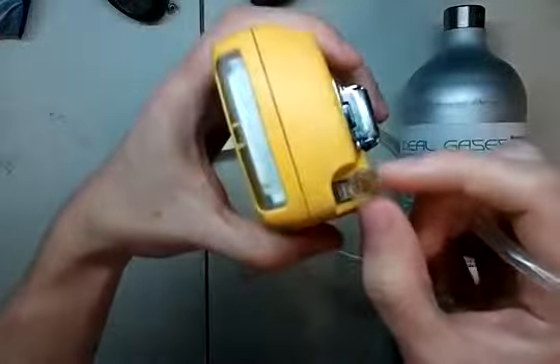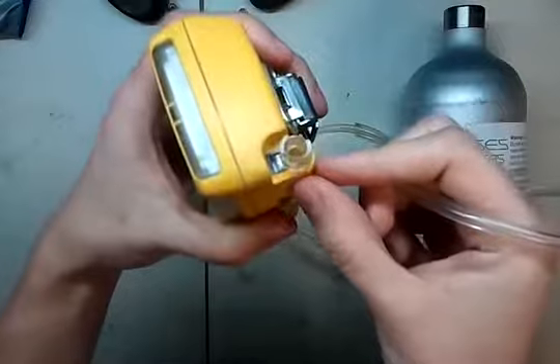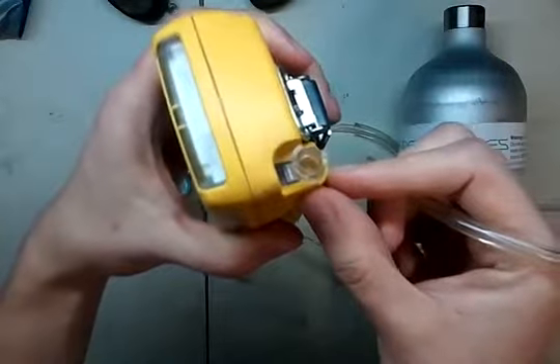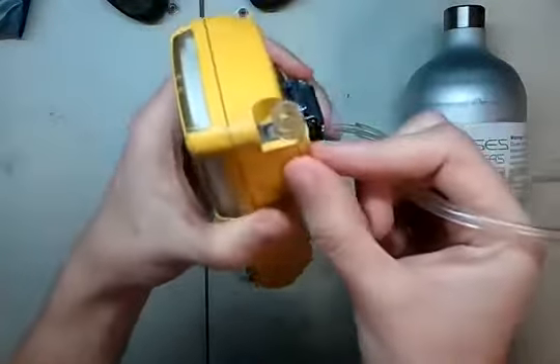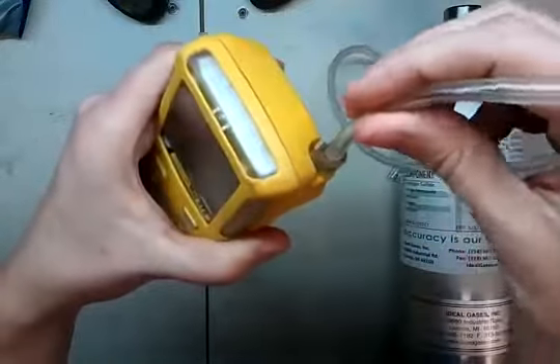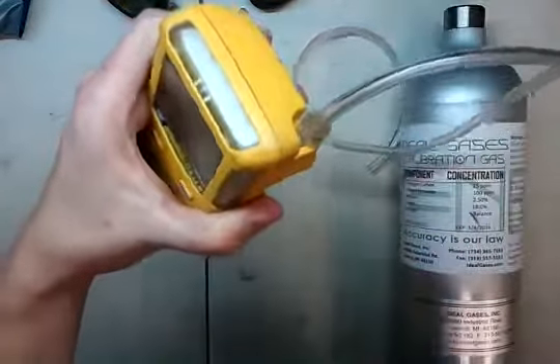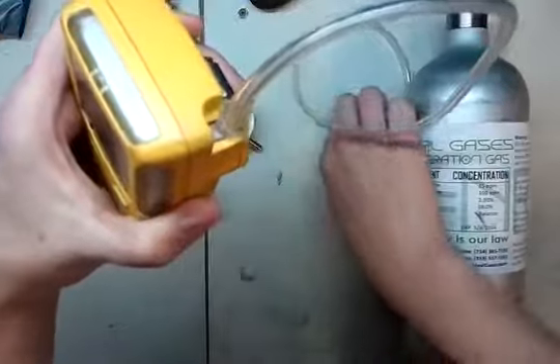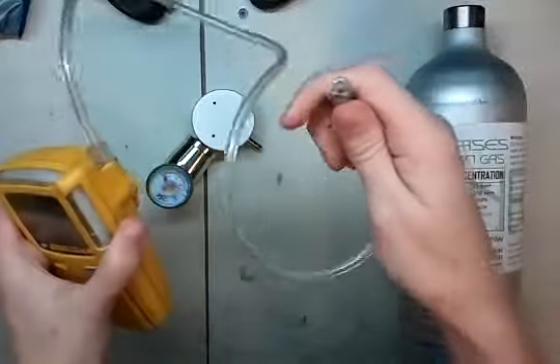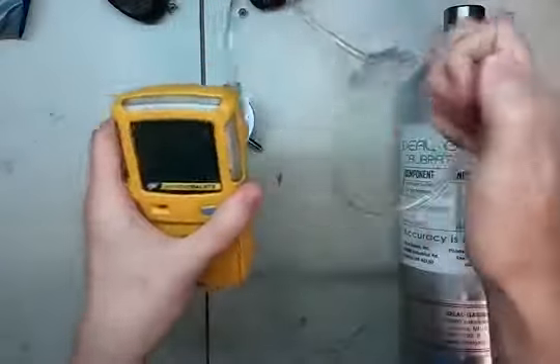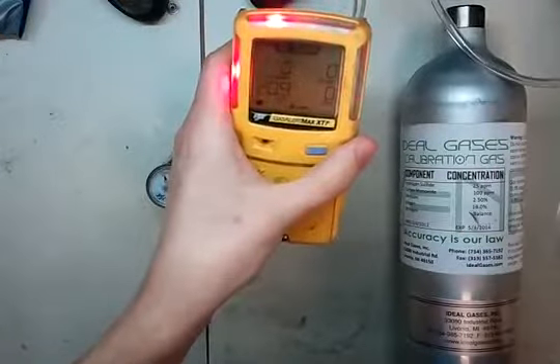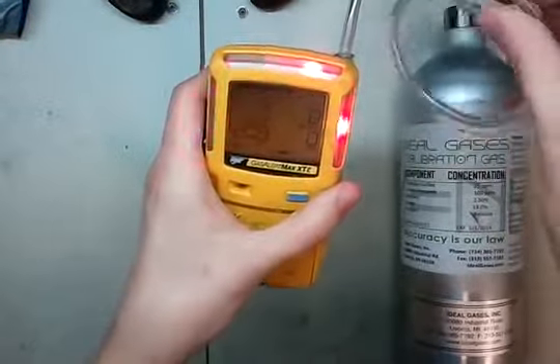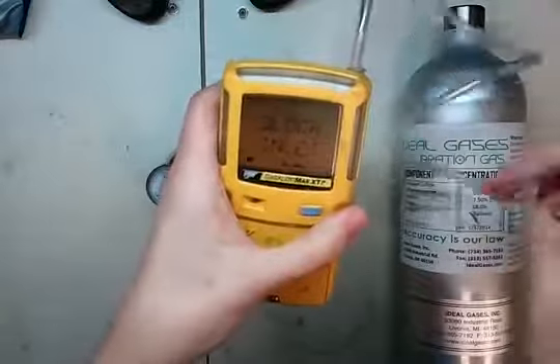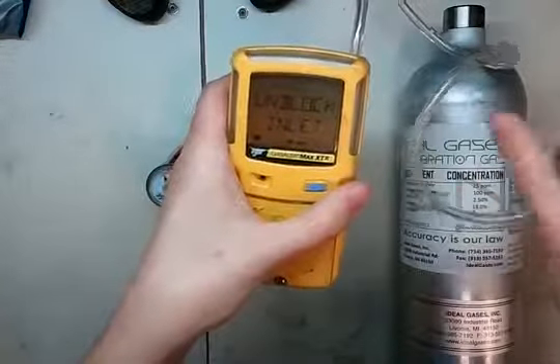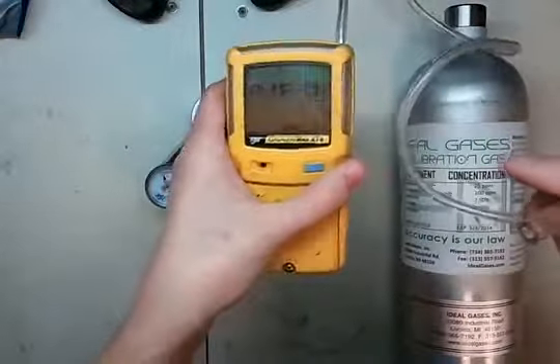Notice also on the other end here, there's supposed to be an adaptation fitting here, but unfortunately we cracked the last one, so I'm waiting for a new one to come in, but wanted to make this video in the meantime. Here's the trick to making sure that your setup still works. Place the inlet tube there. Now take your hose, press your thumb over it. See how it sends it into alarm? That tells us that our system here is airtight. Press the button, block the inlet, unblock the inlet. Okay, now it knows the pump is okay, so we can get to calibrating.